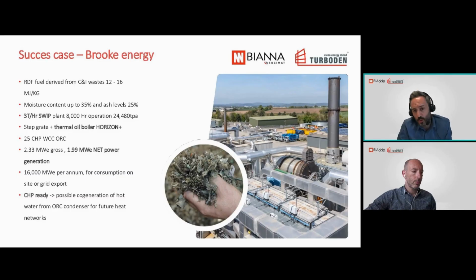This is what we call in the UK a small waste incineration plant, meaning 3 tons per hour is the limit it can process, which means around 25,000 tons per year. The technology, as I will show you later, was a step grate with a Horizon Plus thermal oil boiler. Also it's CHP ready, meaning it can have possible cogeneration with hot water for industries around. Once we've talked about this, let's see it in the video.